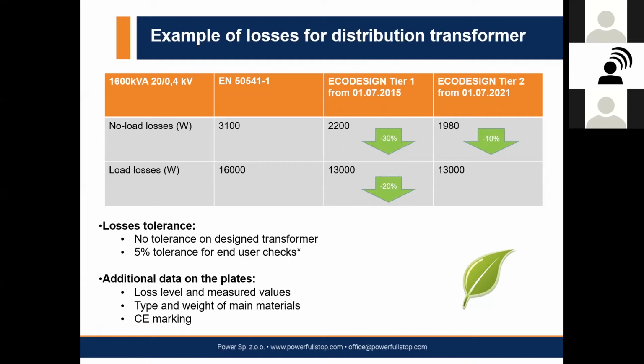It means that we will still have to reduce the no-load losses by 10%. This is absolutely not a problem. Many manufacturers started 1 or 2 years ago, as we did, with production of this kind of transformers. Reducing the losses by 10% is very easy. It's not the same difference we had before. But what is interesting, when the first regulation was published, everybody was convinced that Tier 2 would never enter into force, because it's impossible to reach the numbers they pretend, and impossible to afford the costs of the transformers. Nowadays, we know it's possible.